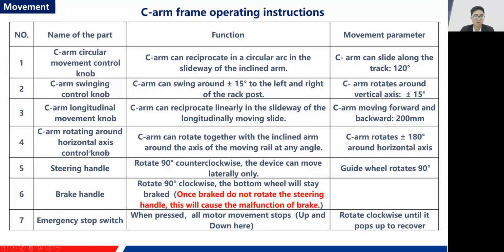Okay, the C-arm rotating around horizontal axis control knob. Unlock this knob, and the C-arm can rotate together with the inclined arm around the axis of the moving rail at any angle, from minus 180 degrees to positive 180 degrees. So that is 360 degrees in all. And for the steering handle, rotate it counterclockwise, and the device can move only laterally. If you rotate it 90 degrees counterclockwise, the wheels behind the C-arm will also rotate 90 degrees, so you can only move the C-arm in the lateral direction. And for the brake handle, rotate it 90 degrees clockwise, and the bottom wheels will stay braked.